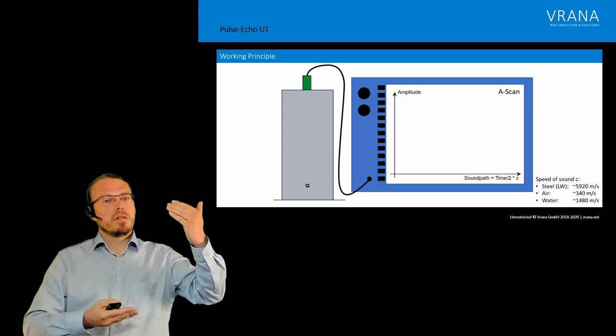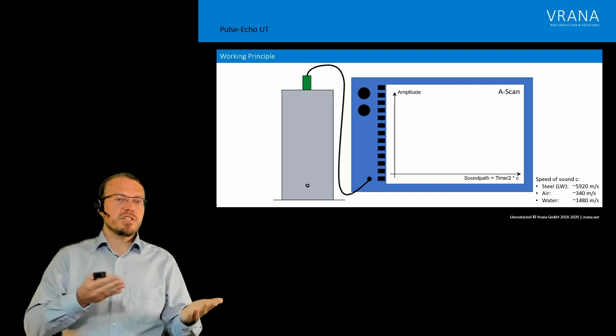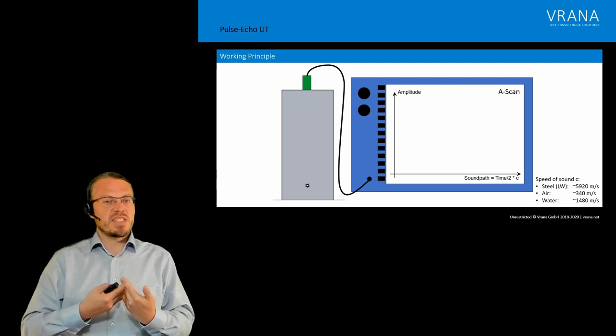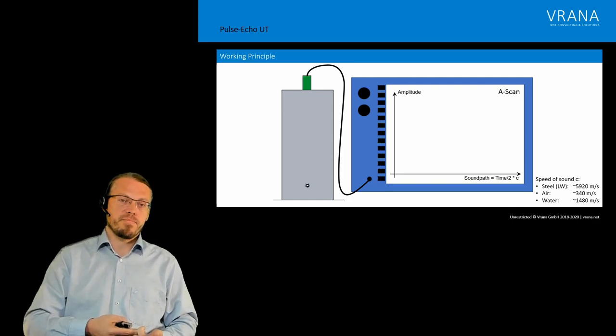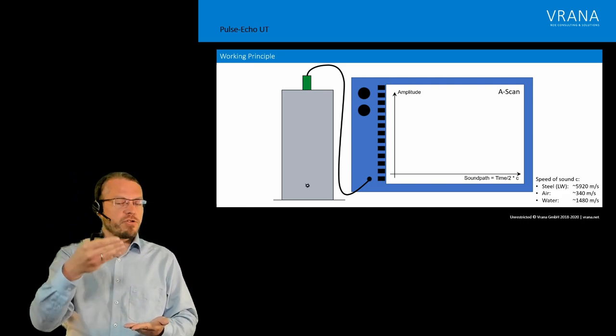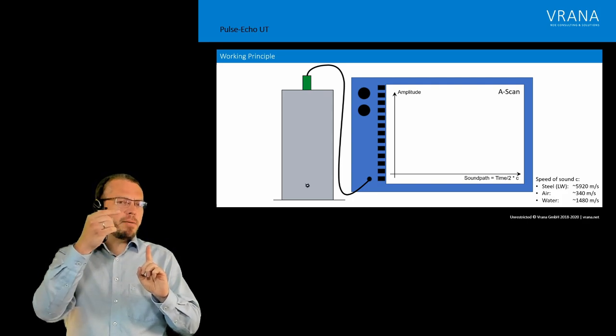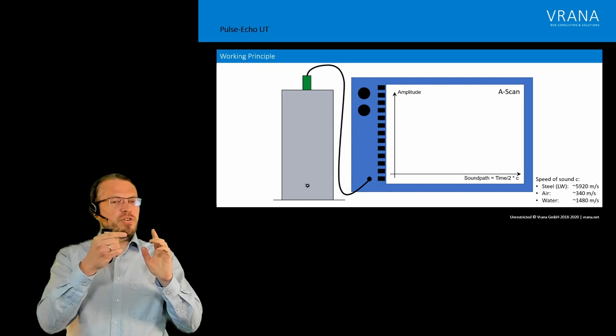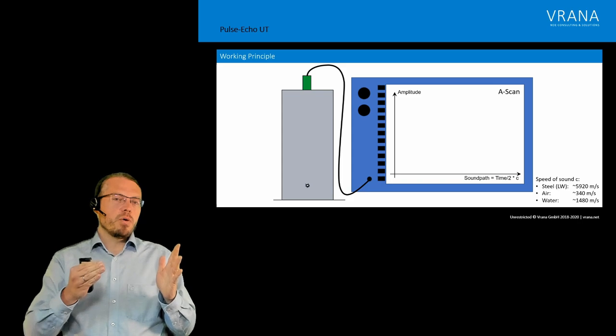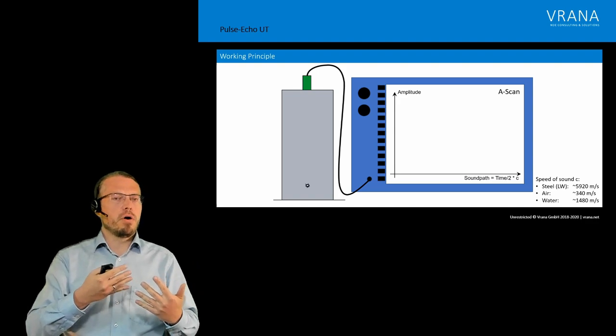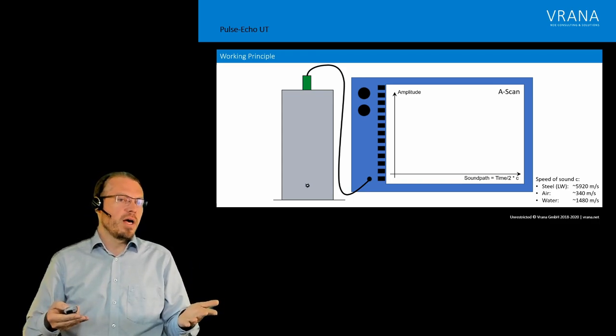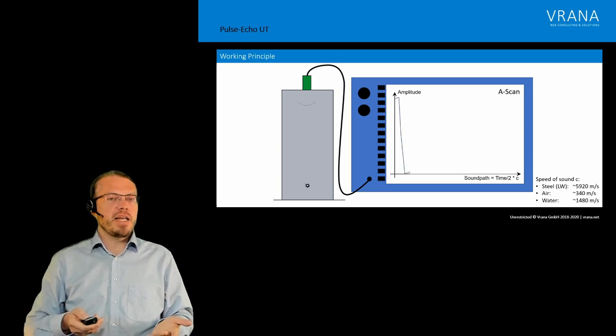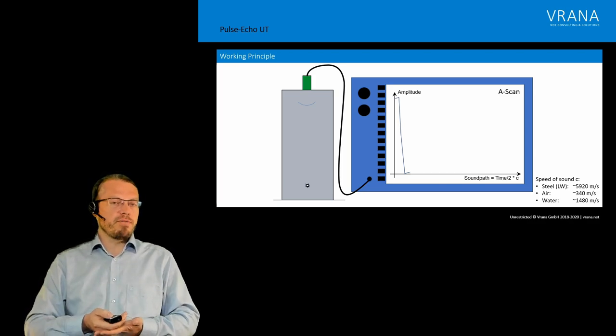What matters is that this liquid actually helps to bring our ultrasonic wave from our probe into our component. Now, once that very short pulse is finished, then the instrument switches from a sending to a receiving mode. And it's this very same probe which is actually used for sending, which is also used for receiving. So now, what happens is we get our acoustic wave exiting our probe entering our component. Or to be exact, traveling back and forth between the probe and the surface of the component within the coupling medium. So during the first few hundred nanoseconds, actually what we will see is only this wave going back and forth. And that actually saturates our probe. So that's why in the beginning we have a so-called dead zone where we do not see anything.